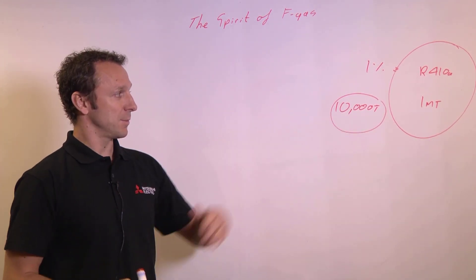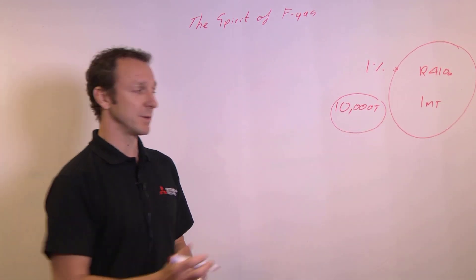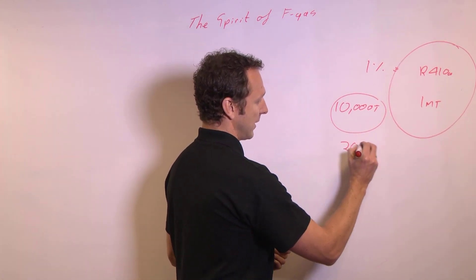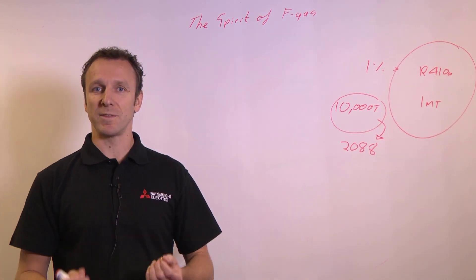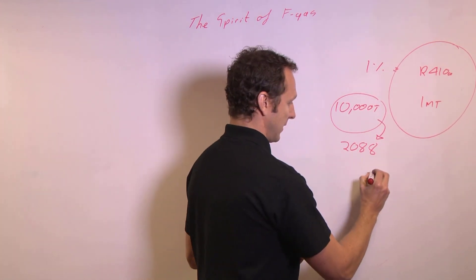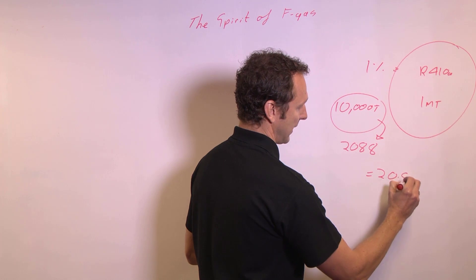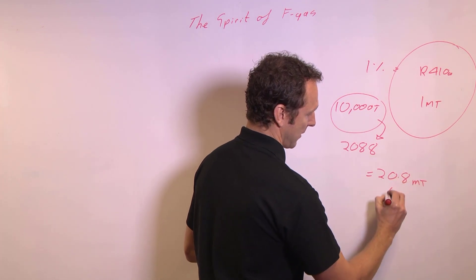Now the story doesn't stop there, because R410A has a global warming potential of 2088. I have to multiply the two together to get the CO2 equivalent that's being released, which is 20.8 million tonnes of CO2.